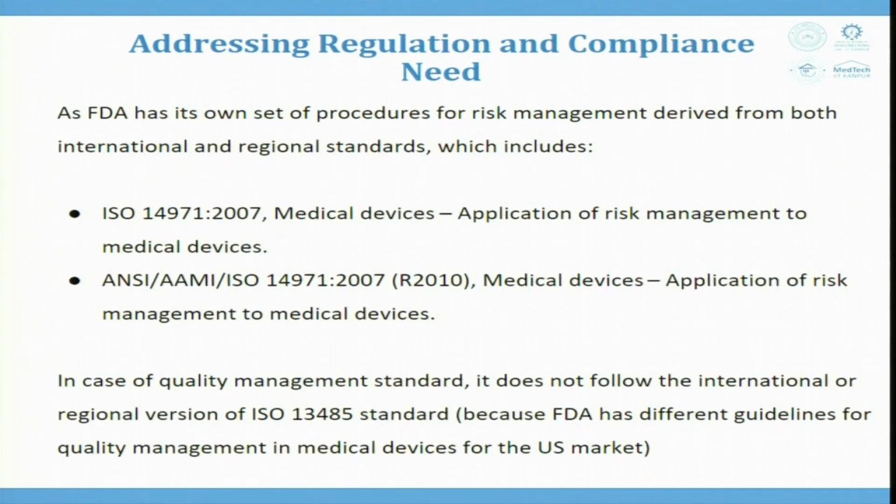Now, FDA has its own set of procedures for risk management derived from both international and regional standards, which include the ISO systems, that is ISO 14971 2007 medical devices, application of risk management to medical devices, and ANSI AAMI ISO 14971 2007, that is R2010 medical device, application of risk management to medical devices. In case of the quality management standard, it does not follow the international or regional version of the ISO 13485 standard, because FDA has different guidelines for quality management in medical devices for the US market.